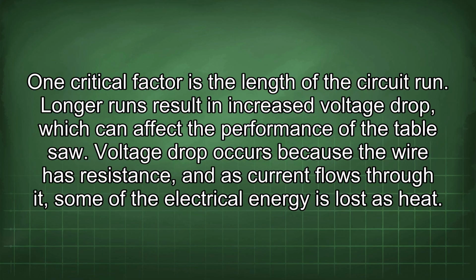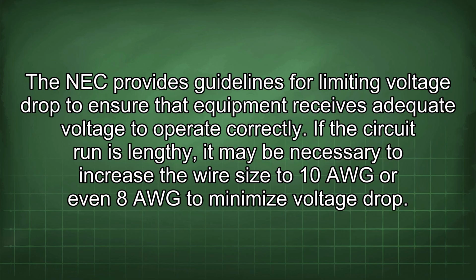One critical factor is the length of the circuit run. Longer runs result in increased voltage drop, which can affect the performance of the table saw. Voltage drop occurs because the wire has resistance, and as current flows through it, some of the electrical energy is lost as heat. The NEC provides guidelines for limiting voltage drop to ensure that equipment receives adequate voltage to operate correctly. If the circuit run is lengthy, it may be necessary to increase the wire size to 10 AWG or even 8 AWG to minimize voltage drop.